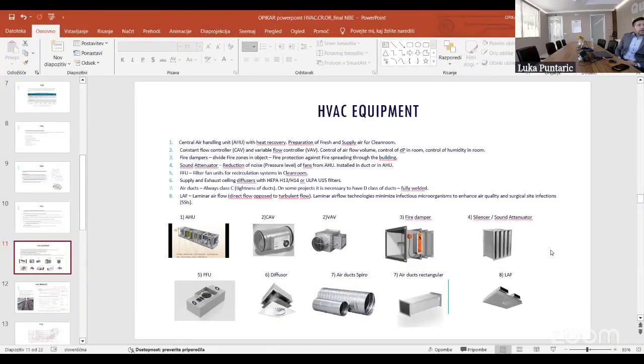Diffusers with HEPA or ULPA filters, high efficient filters that eliminate all the particles. We have our air ductwork, which is in a round shape or rectangular shape, normally made by galvanized steel, normally in tightness class C. They can also be fully welded, which means class D. Laminar airflow on the end is especially designed for operating rooms. So laminar airflow technologies minimize infections and microorganisms to enhance air quality and reduce surgical site infections. This will be shown also in the presentation later.